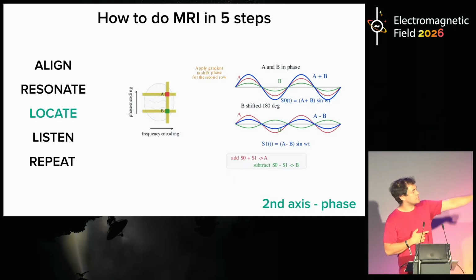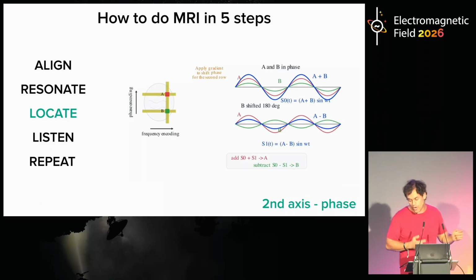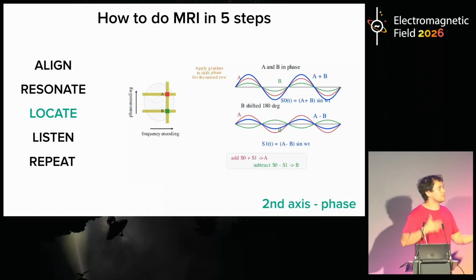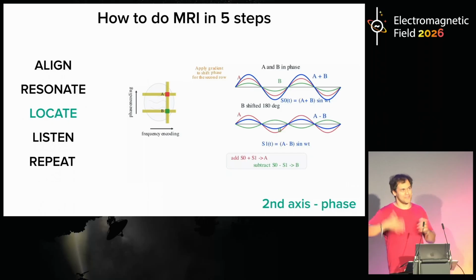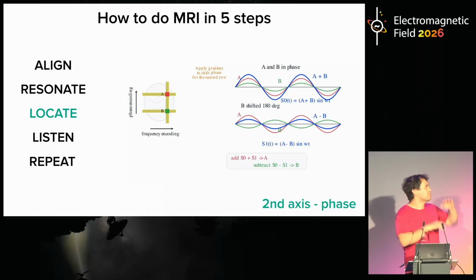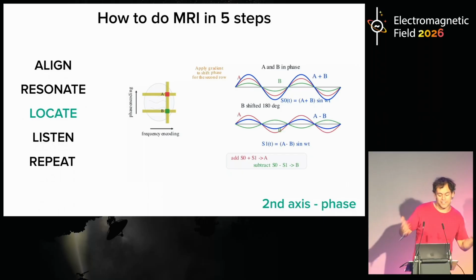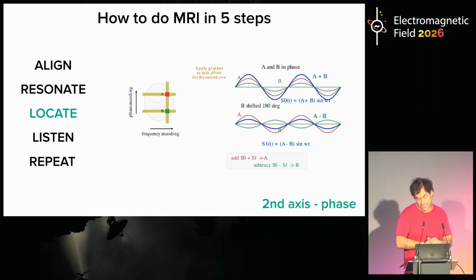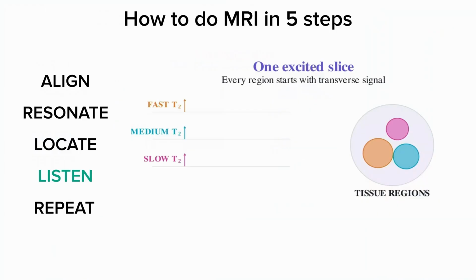And what that essentially does is it changes your phase. So if you can see, you've got these two nice little diagrams here. With one, they're both in sequence with each other, so you've got A plus B. The second one, we've moved B 180 degrees, so then you've got A minus B. And then it's pretty simple maths. You add the two together, the A's will add, the B's will cancel, you get A. You subtract the two from each other, the A will cancel with the A, and the B will add with the minus B, which will give you B. So that's a really toy example for two lines, but you can extend it to get as many lines as you want, and it's one of those things that you had in school, many equations, many unknowns. And then the fourth step, bear with me here, is you need to listen for it.